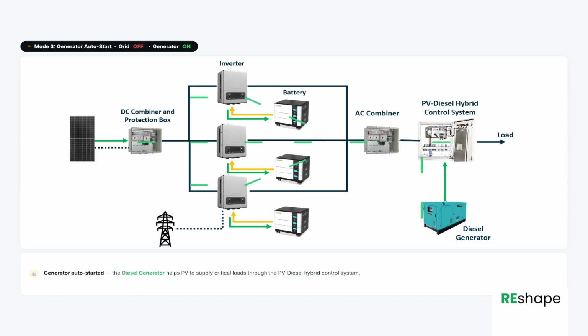In the grid outage mode where the grid is off but the generator is on, in this mode the generator will help PV to supply critical loads. It will also charge batteries per configured set point to keep battery SOC healthy.